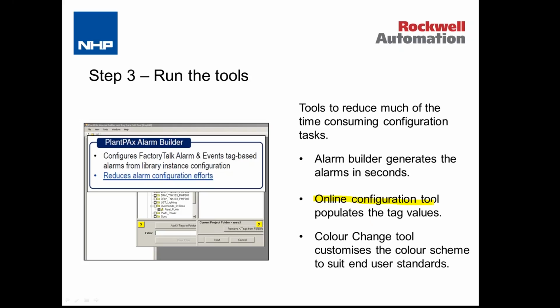That's an Excel-based tool which allows us to, via RSLinx, connect to the controller and to configure the objects. By that we mean we can specify which alarms are enabled, which alarms are disabled. We can specify the alarm descriptions, the alarm delay times. We can configure a valve as to whether it has open and closed feedback or not. Pretty much everything that is typically configured on these objects we can do via this spreadsheet.